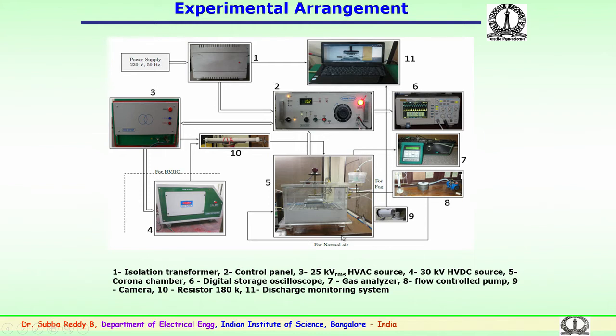And finally, the corona process: during the corona activity inside the chamber, the gases which are formed, nitrous oxide and many of these, we are measuring using a gas analyzer, which measures the gas formed in this chamber. So, it is a very important arrangement for long duration studies of the corona performance on the samples.